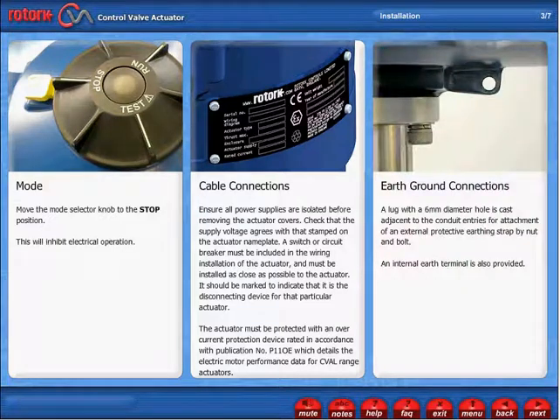Earth Ground Connections. A lug with a 6mm diameter hole is cast adjacent to the conduit entries for attachment of an external protective earthing strap by nut and bolt. An internal earth terminal is also provided.